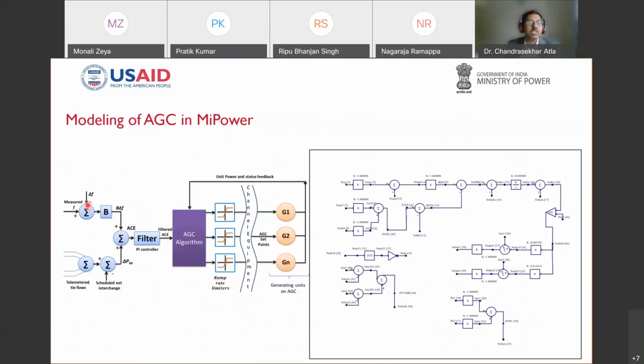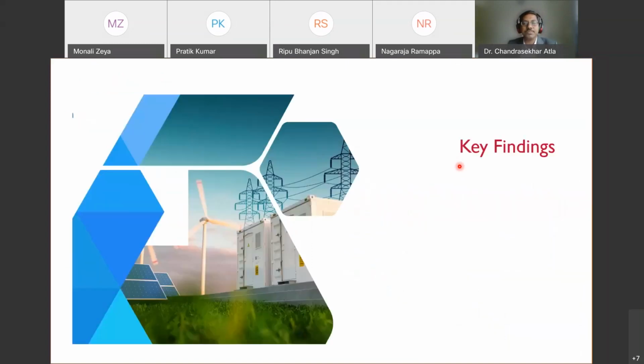Once this frequency is there, based on the bias factor, area control error will be generated, and that error is controlled through the PI controller and given to the generators considering their ramp rates. The actual generation is monitored back to the AGC logic, and it all has been developed under the closed loop environment. The right side shows the blocks implemented to simulate the AGC operation in MiPower software.